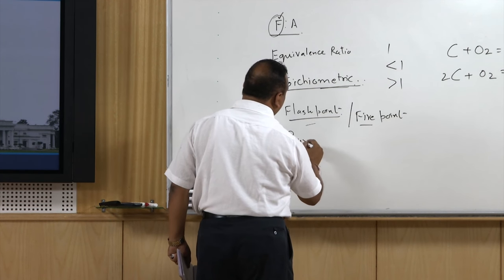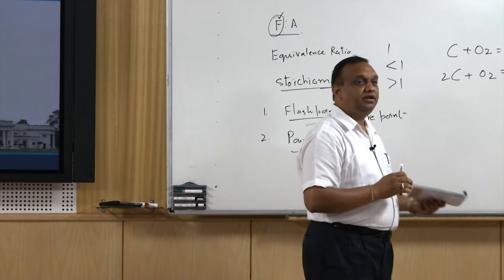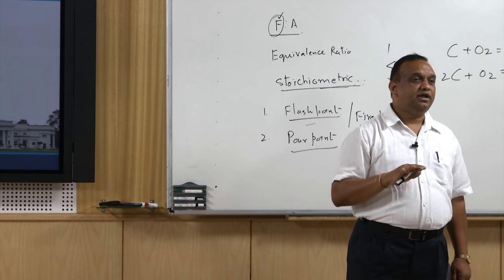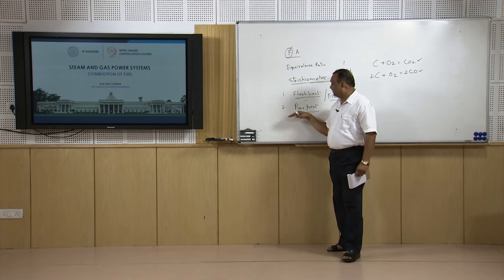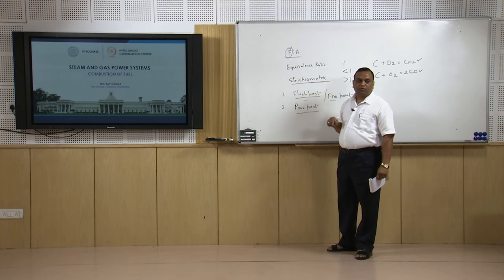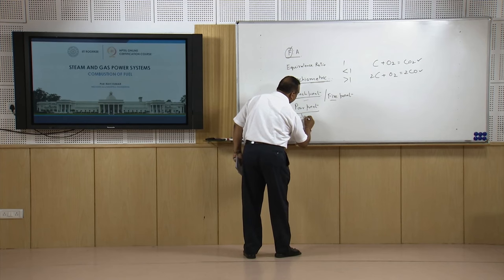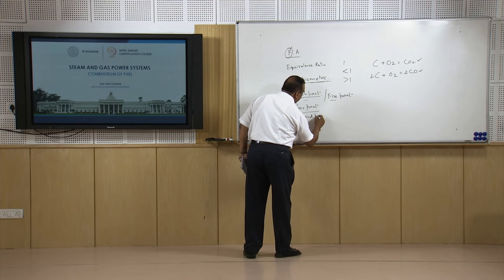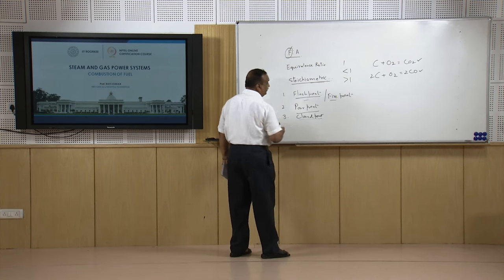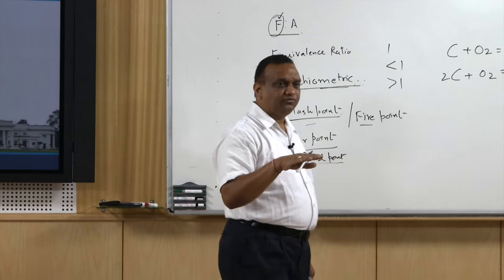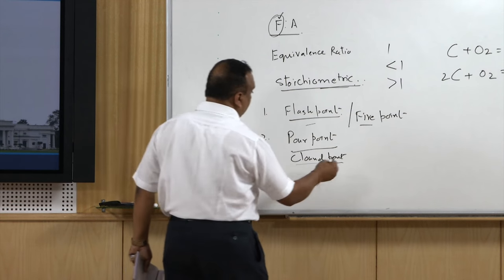The second characteristic is pour point. These are all physical characteristics of the fuel. Pour point is the minimum temperature at which the liquid fuel is flowable. There is another term called cloud point — the temperature at which solidification of wax present in the fuel takes place, causing the surface to become whitish.